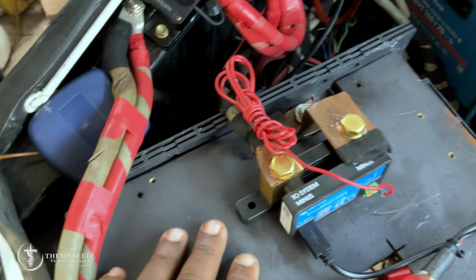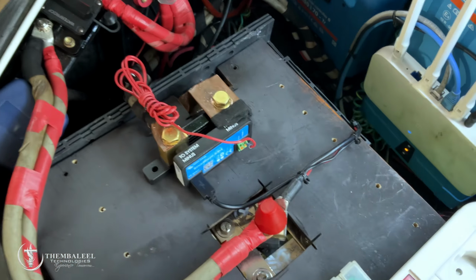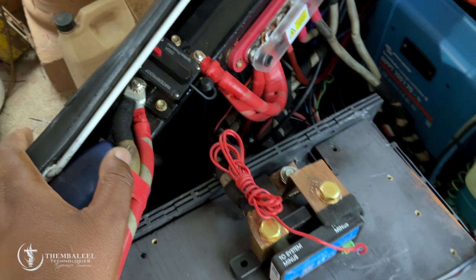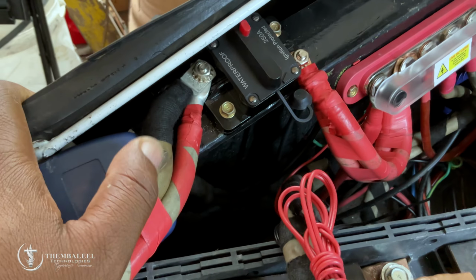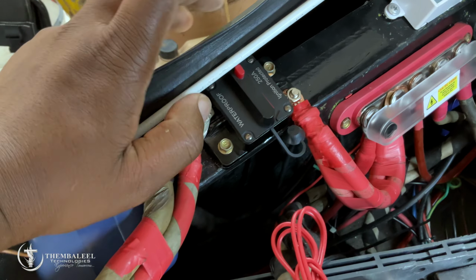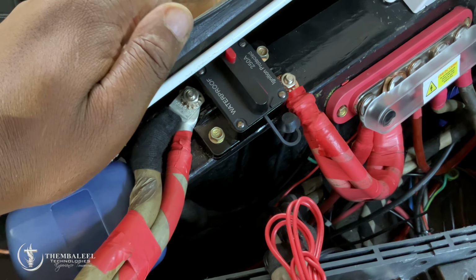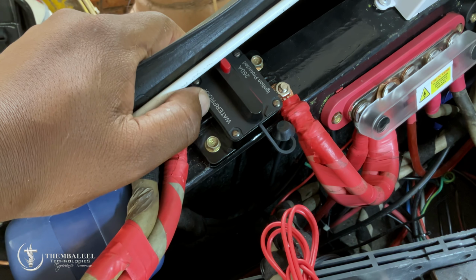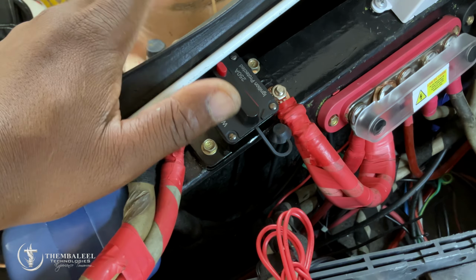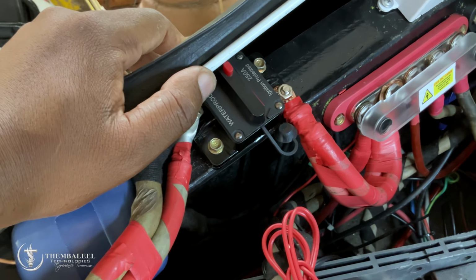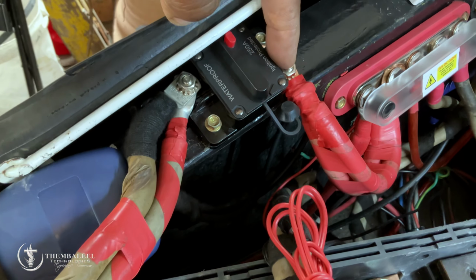I was influenced by the fact that the battery bank is 400 amp, so I had a 100, 200, 250, 300 and 400, and they just label them like that. It's not true - when I tested, this goes at 180 amps and then it trips. 180, 190, it trips. So pay attention to the terminals.